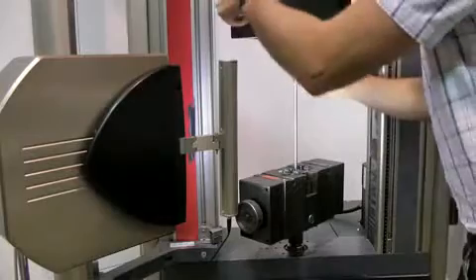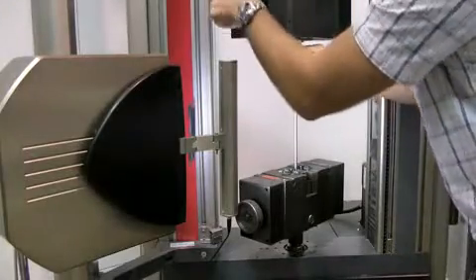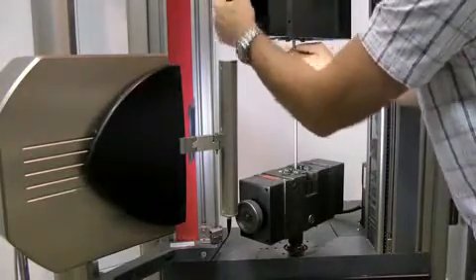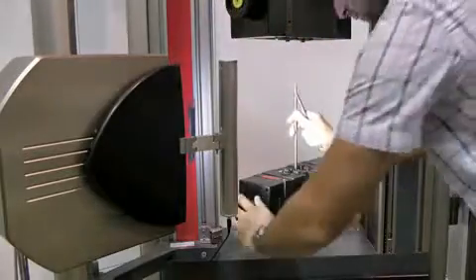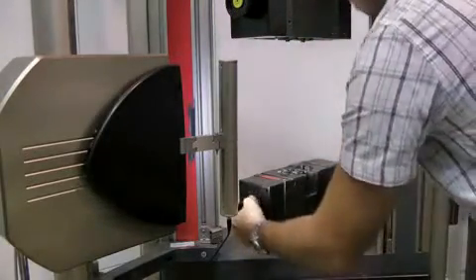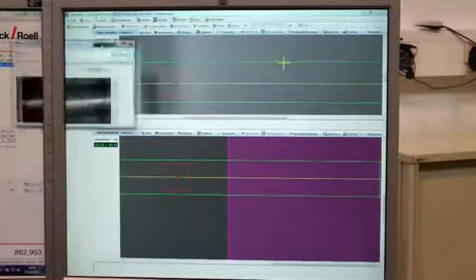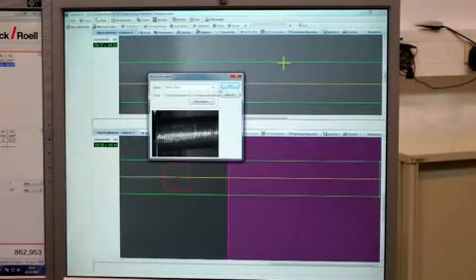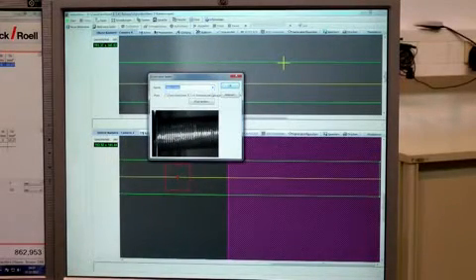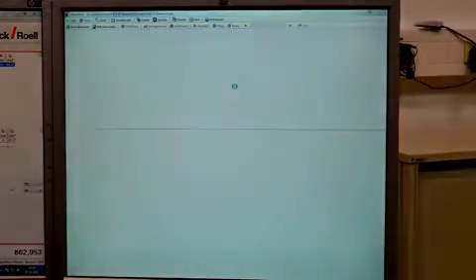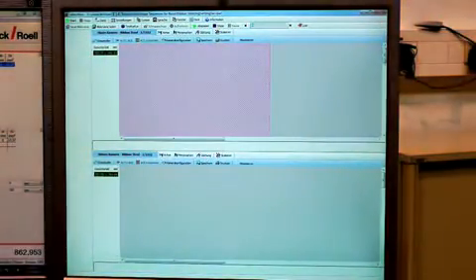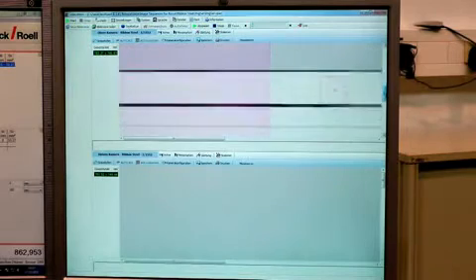Luckily the videoXtens has a function called videoXtens RERUN. The videoXtens records the images during the test and afterwards we have an image sequence which we can re-evaluate. That means we open the image sequence and check where the necking and the breaking point of the rebar steel was.